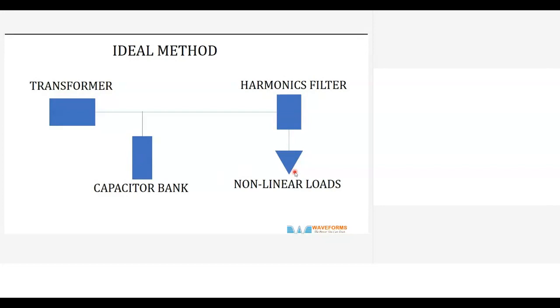Sometimes when you filter these harmonics and the harmonics are lesser than, say, 7 to 8%, then you may not need these inductors, these reactors. But there's no harm in adding reactors. The only thing is they may consume some power and electrical efficiency may suffer a little, so that issue will be there. So it is a trade-off whether you require reactors or not. It depends on the situation; you have to take a call depending on the level of harmonics. The ideal way is filtering it closer to the source.